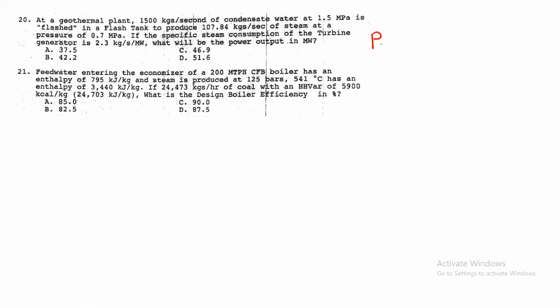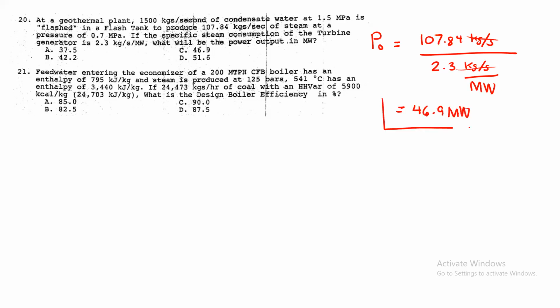So, power output PO is equal to, so, meron tayo ditong mass flow rate, no? So, 107.84 kilograms per second, divided by, ito, may specific steam consumption. So, 2.3 kilograms per second per megawatt. So, maka-cancel na to kilograms per second. So, matitira dito is 46.9 megawatts. So, ganyan lang siya kadali, guys.